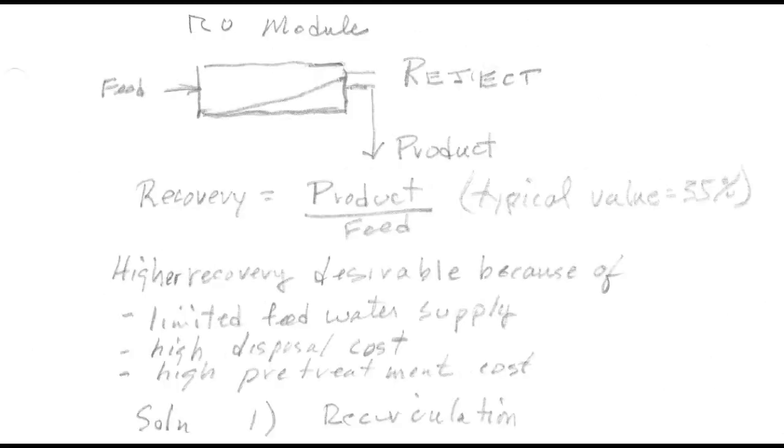Reverse osmosis modules are usually diagrammed in this manner, which is the way it's done in our book. Feed coming in from the left, a membrane, the permeate or product water going out and down on the right, and the reject water going out to the right. The recovery is the product quantity divided by the feed quantity, and a typical value is about 35% per stage. Higher recovery is very desirable in many situations.